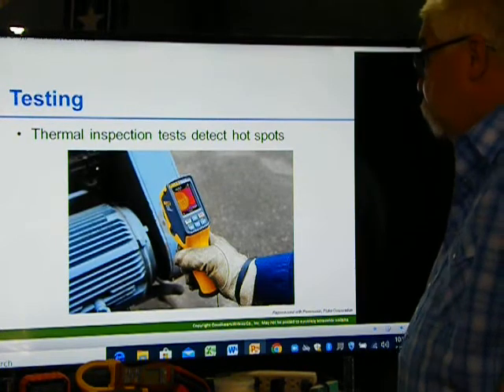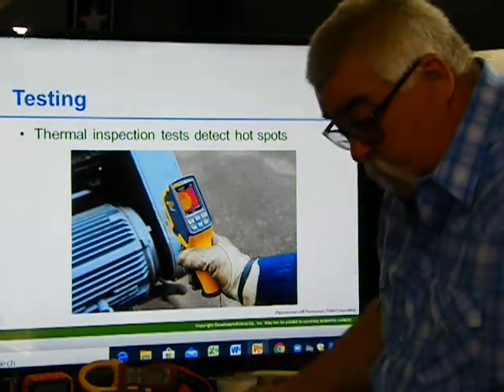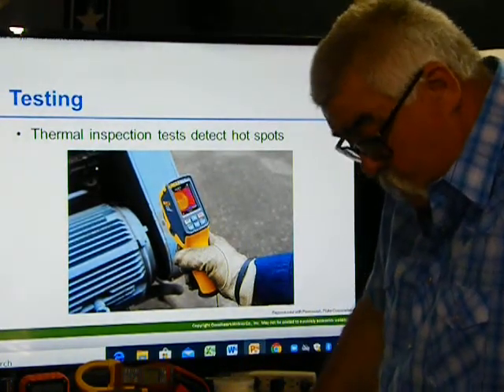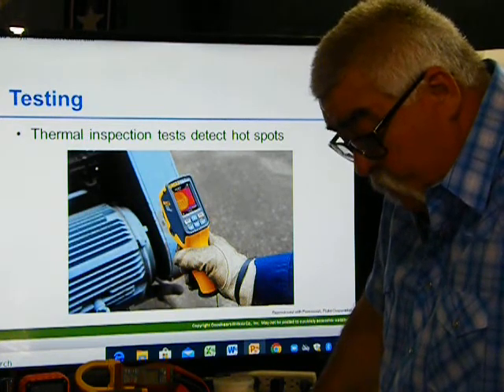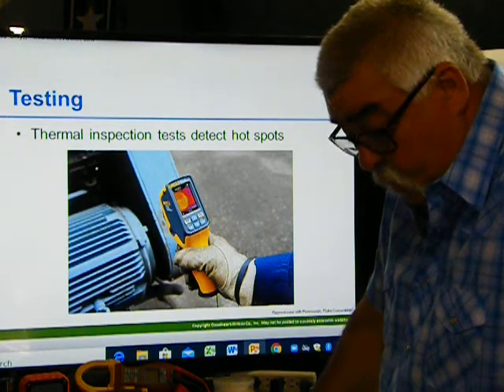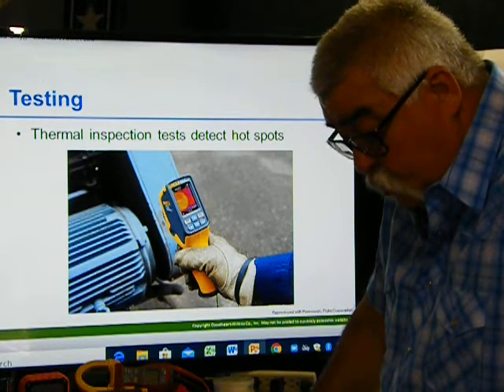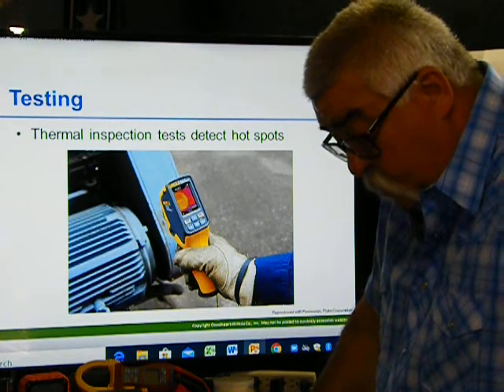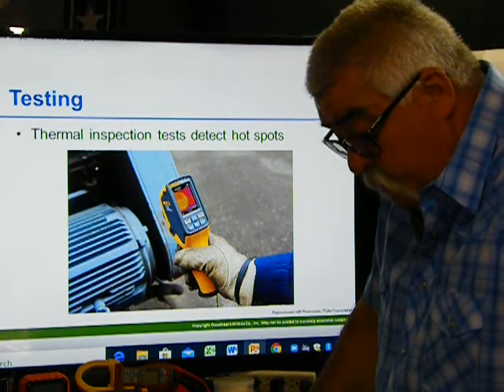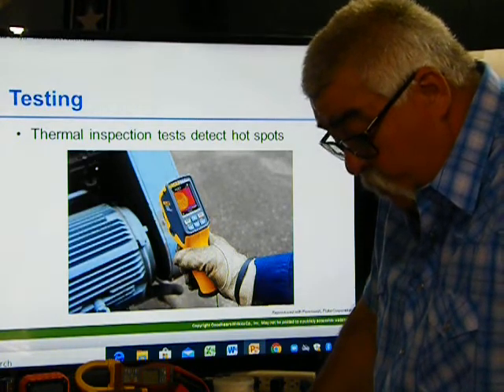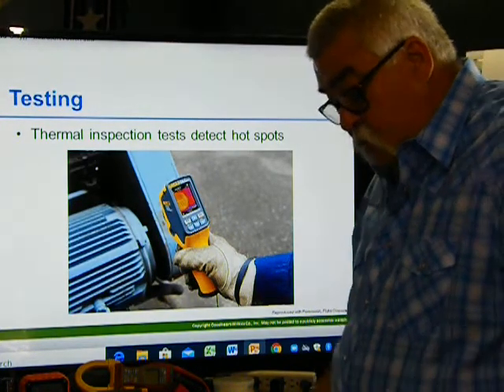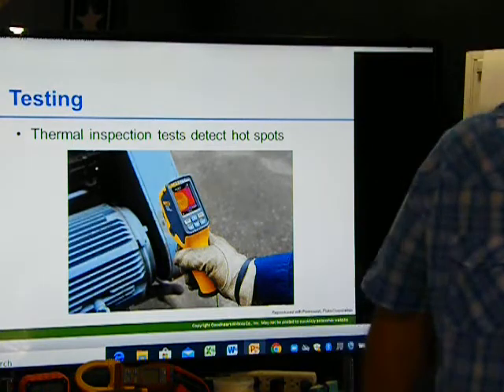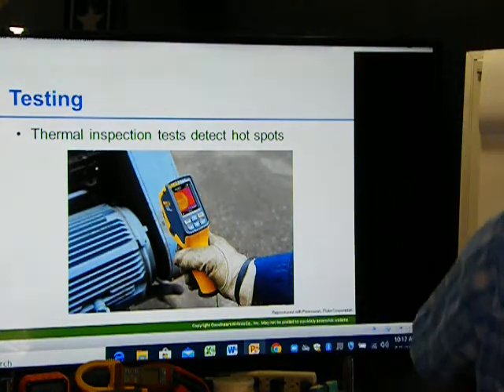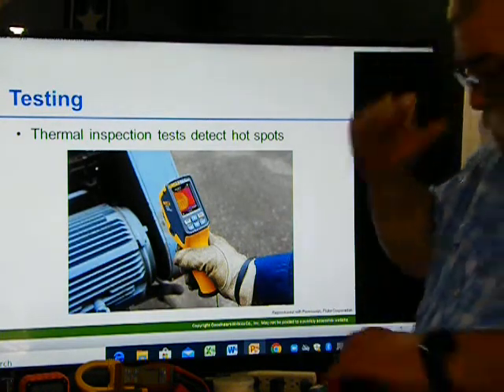Okay, thermal inspection test detects hot spots. So using the thermal reader, this test is used to detect hot spots in switchgear, motor control centers, and other parts of the electrical system. This is an effective way to determine bad splices. So sometimes when we have breakers tripping or anything, we have a special infrared camera.